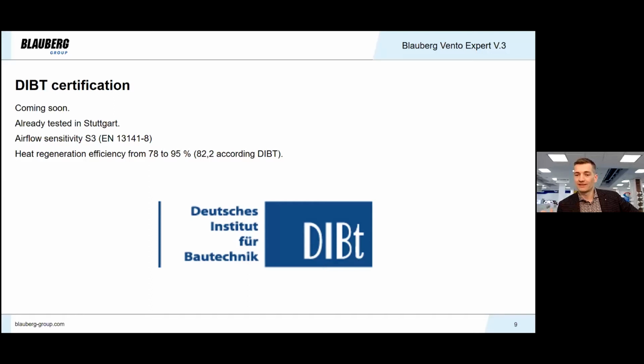Improvements that we will see next made possible to achieve S3 class in airflow sensitivity and to reach one of the highest heat regeneration efficiency at the market. For example, it is from 78 up to 95% according to this European norm that I have already mentioned, or 82.2% according to DIBt. So this is the best DIBt heat recovery efficiency that we have achieved in all our products. We will be able to provide you with test reports on your request, of course.